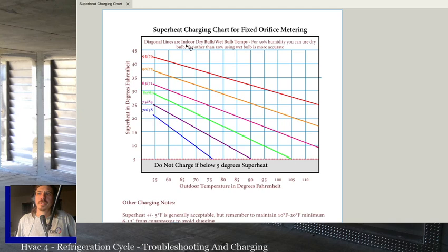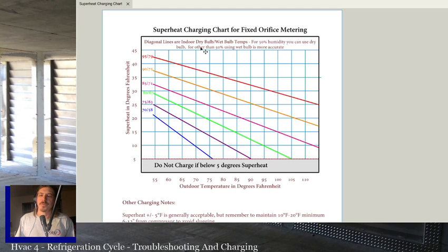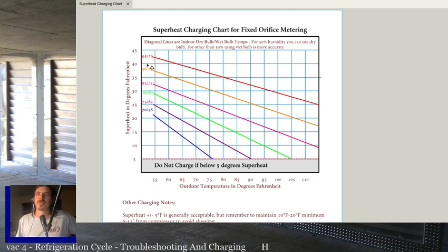For 50% humidity, you can use dry bulb. Other than 50%, using wet bulb is going to be more accurate for charging superheat. I generally say as long as I'm somewhere between 40 and 60, and here in our area we're usually going to be closer between 50 and 60. As long as the humidity is not crazy inside the house, then you're fine using dry bulb. But if you can get a psychrometer in there and actually check wet bulb, or calculate wet bulb using the relative humidity inside the house or inside the return duct, then using that wet bulb number will get you much closer to where you need to be.